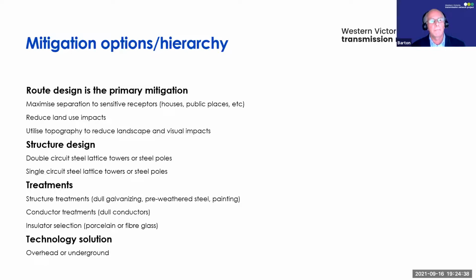route alternatives will be investigated. Through that process we'll seek to maximise separation to sensitive receptors, reduce land use impacts on farming activities and other land uses, and utilise topography where we can to reduce landscape and visual impacts. When that has been exhausted, we then look to structure design, whether it's double circuit steel lattice towers, as seen in the opening slide, or steel poles, or single circuit steel lattice towers or poles, noting that the latter can increase the clutter of structures in the landscape.